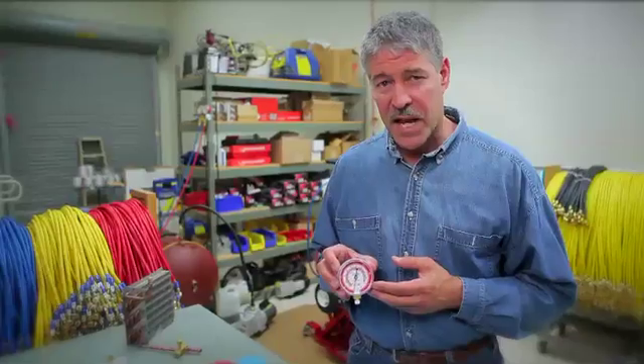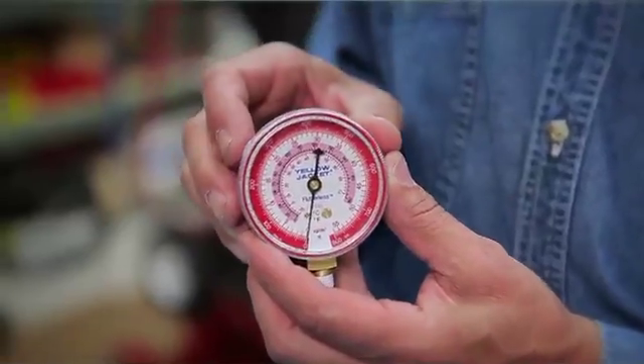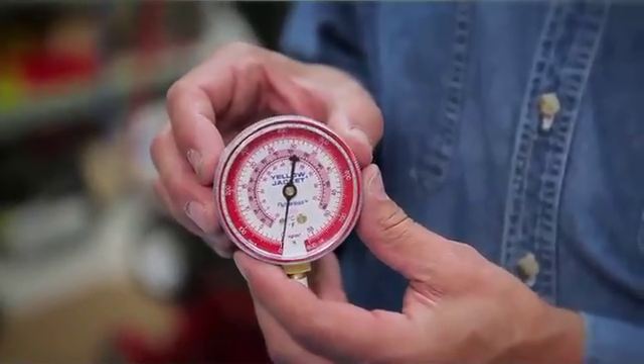Pressure gauges are classified as either analog or digital and are rated by their precision as it relates to the scale of the gauge. They typically come in two options. The first is 3-2-3, or Class B gauges. With Class B gauges, the positive pressure range is divided into three sections. The middle half of the range is the most accurate, within 2% of the full scale. The first and last quarters of the gauge are accurate within 3% of the full scale.